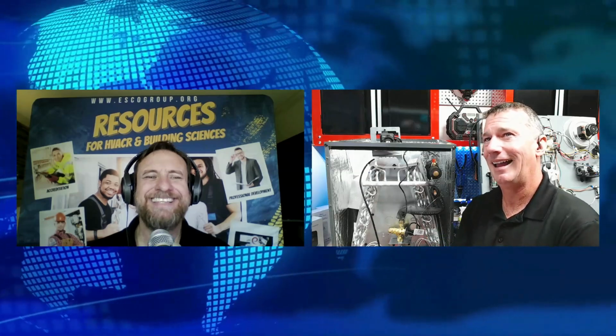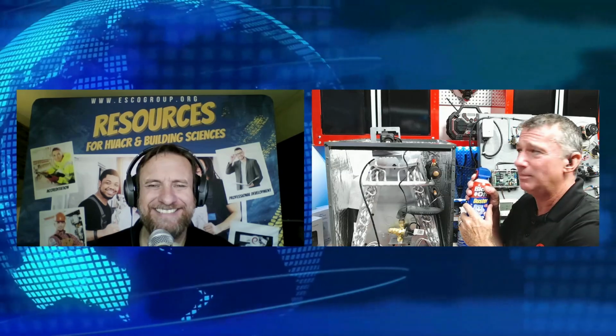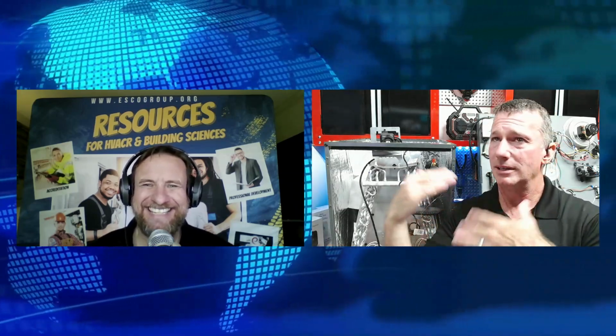Okay, are we ready? Yes. All right, here we go. Very smallest amount that I can pull on that trigger. Look at that. Within 5 seconds, did you hear that click? I didn't even hear the can spray, but I did hear the click. Yeah, a very small amount of refrigerant as I could put onto that sensor. Now, I don't know what that concentration was. I'm going to be working on that on some videos over the next couple of weeks.